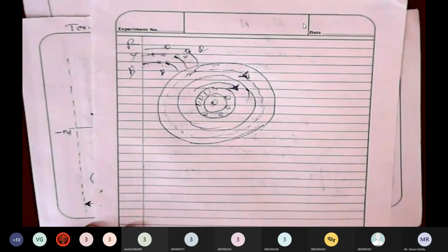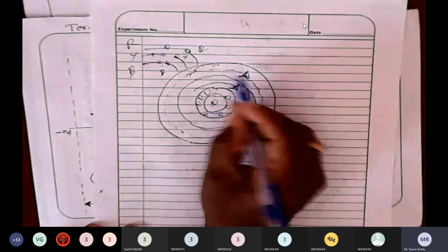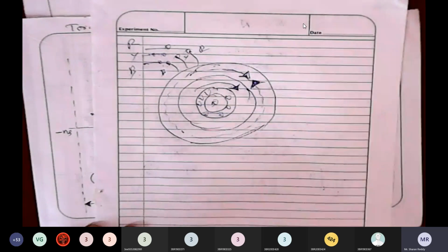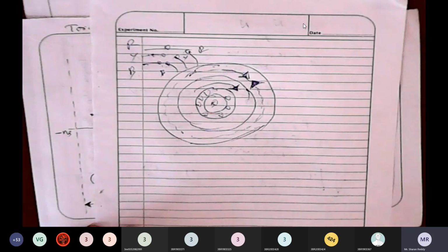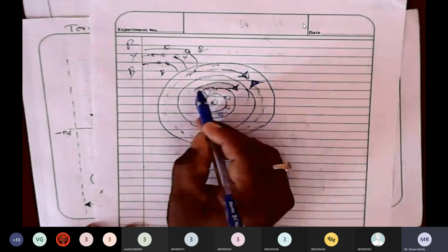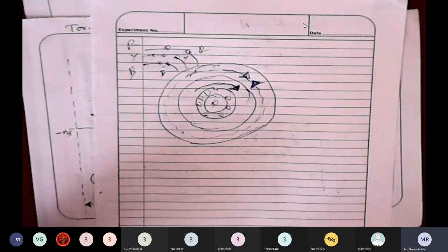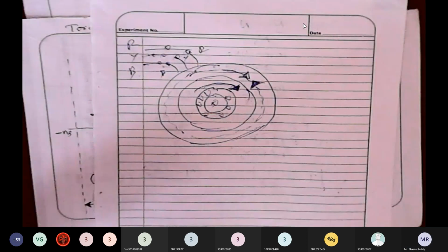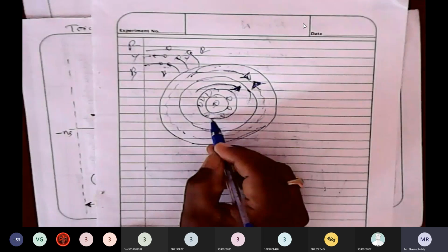What happens, you know? The rotating magnetic field changes its direction. It was rotating clockwise, now it will rotate anti-clockwise. But the rotor doesn't know; it is still running in the clockwise direction. Immediately when you reverse the terminals, an opposite torque is exerted. We are applying the brake to the rotor, which means it stops immediately.